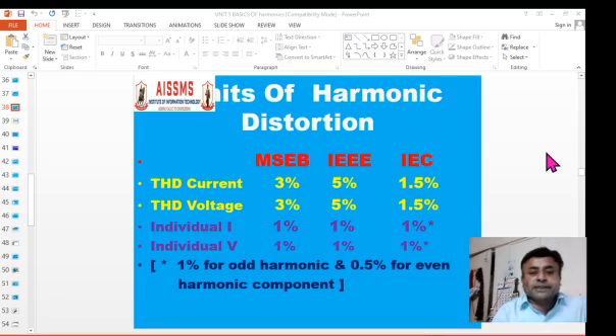Now, today we'll have a discussion about different harmonic standards which are laid down by different statutory organizations. As we have seen last time, the total harmonic distortion for current and voltage has been laid down by MSEB, IEEE and IEC. MSEB states that the permissible limit for THD current and voltage is 3%, whereas IEEE states it to be 5% and IEC states it as 1.5%.